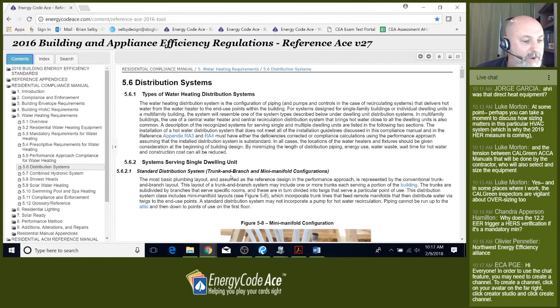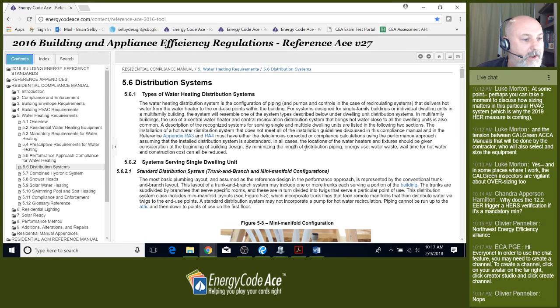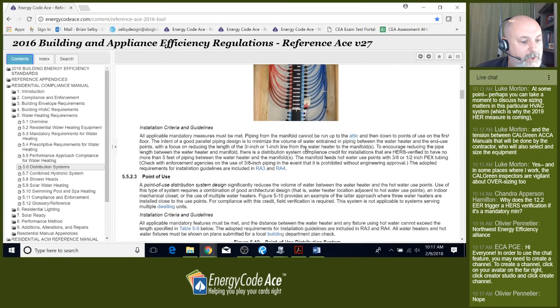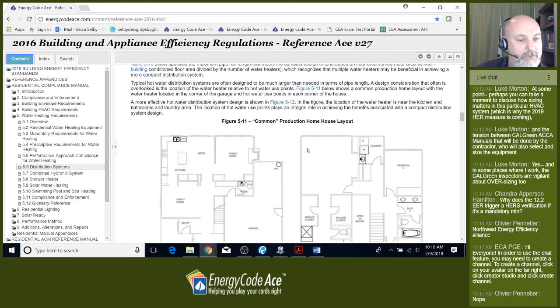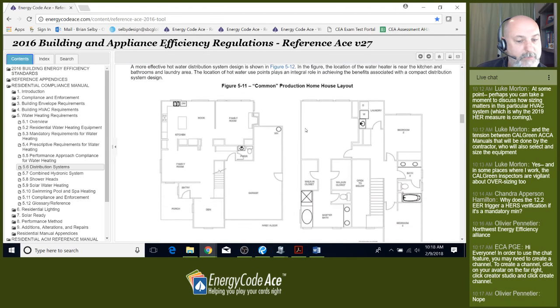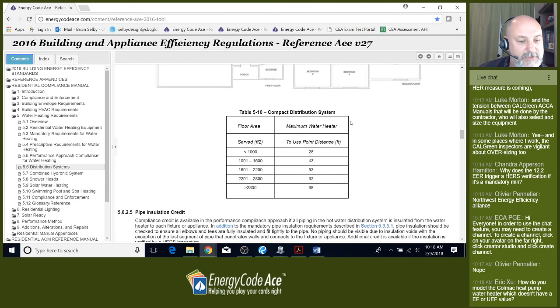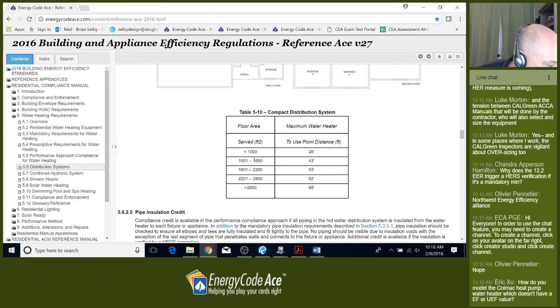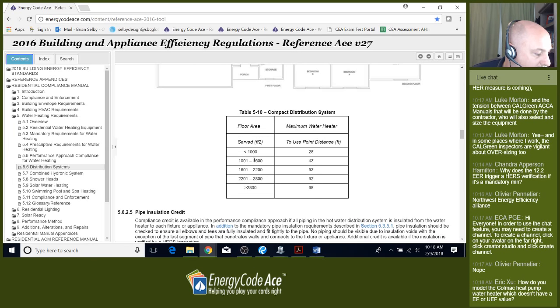Eric's question about the Colmac heat pump water heater without an EF or UEF — I'm not familiar with that one; please send me an email and I can help offline. Our house is between 1,600 and 2,200 square feet, which gives us a total distance of 53 feet. We just need to make sure the distance from our source to the furthest fixture is less than that. Per reference appendix RA4416, the length from the water heater to the furthest use point shall be equal to or less than what's in the table, measured horizontally. The system piping must take the most direct path.